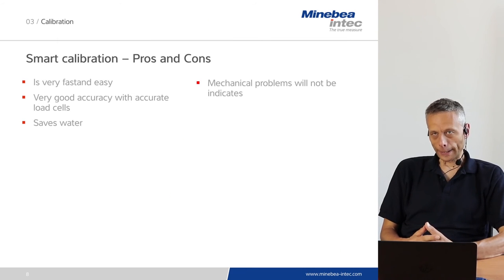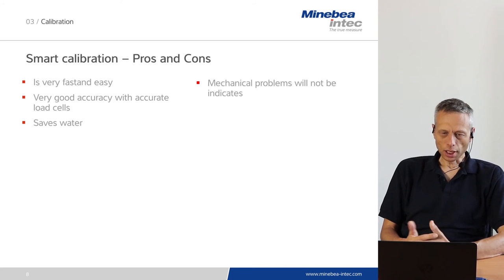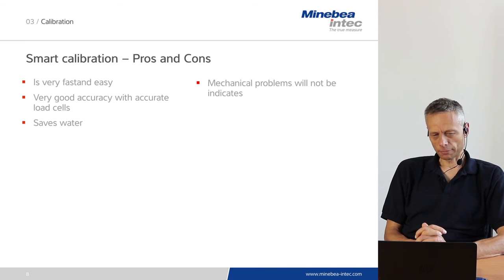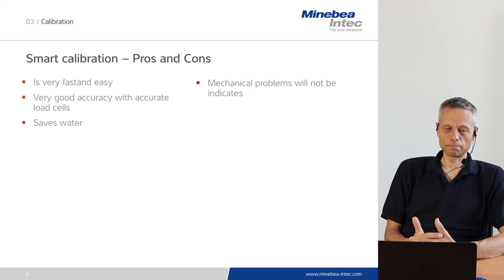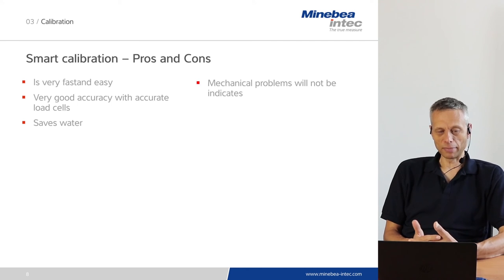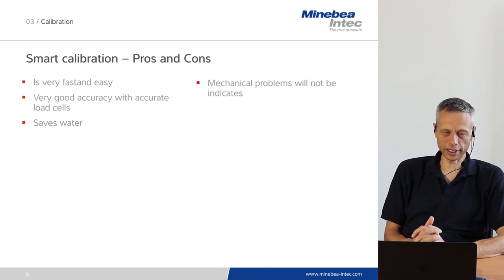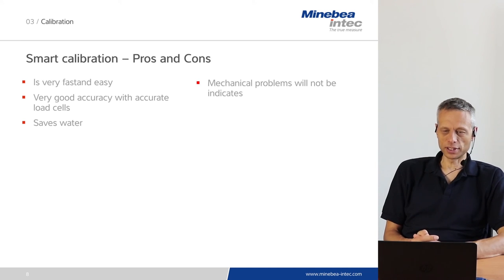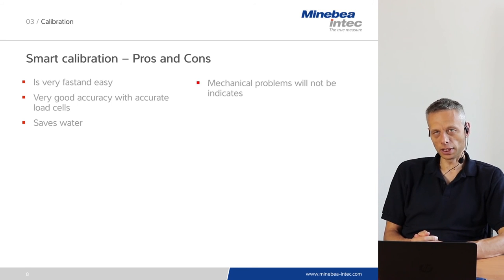We have seen the practical demonstration of smart calibration. As a summary, we can state that this method is very fast and easy. The accuracy will be very good with accurate load cells and a good mechanical setup. The method also saves a significant amount of water compared to calibration with water. The only con is that mechanical problems, if any exist, will not be indicated.